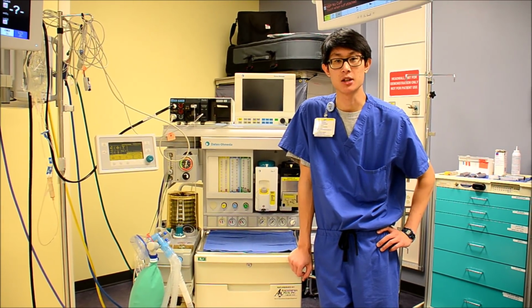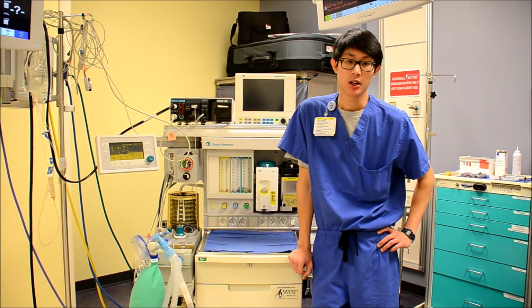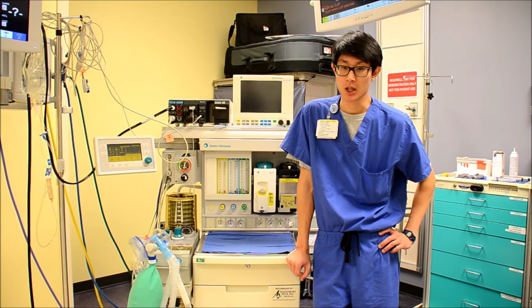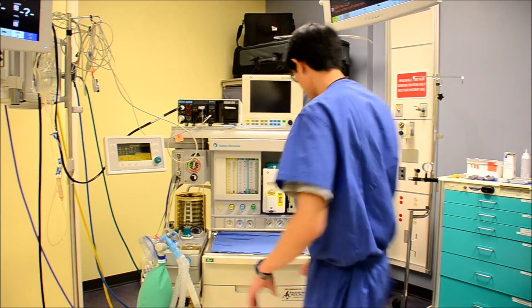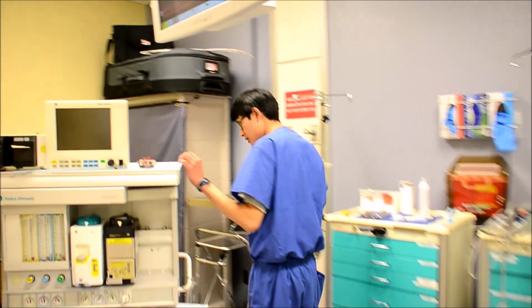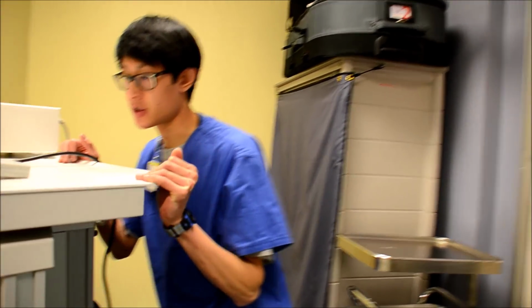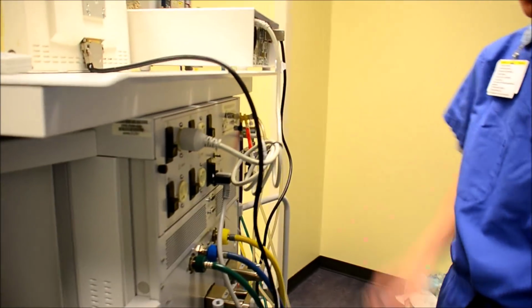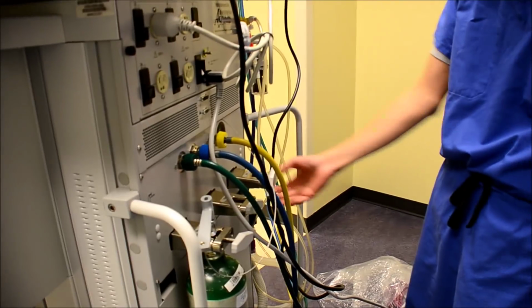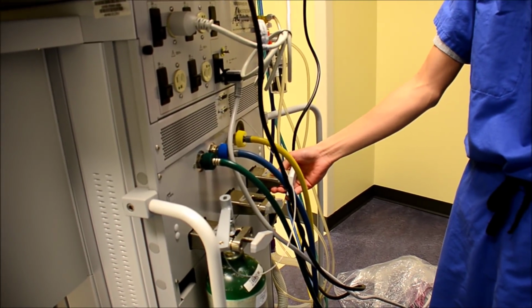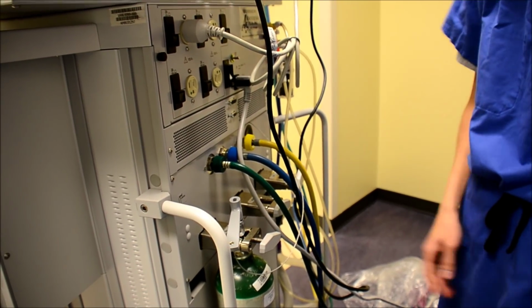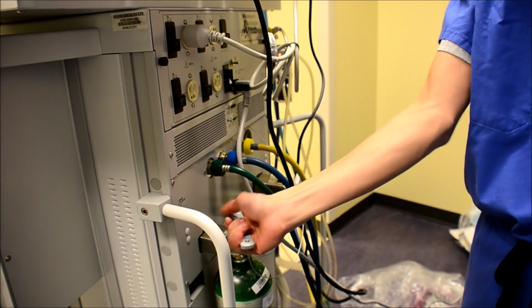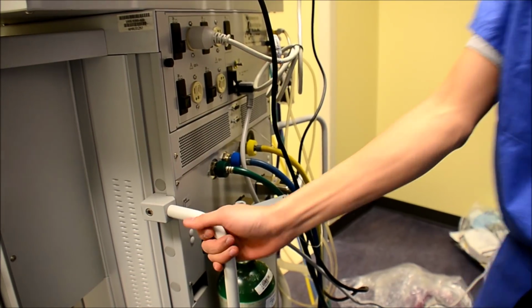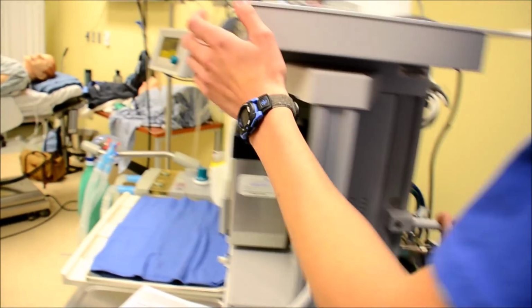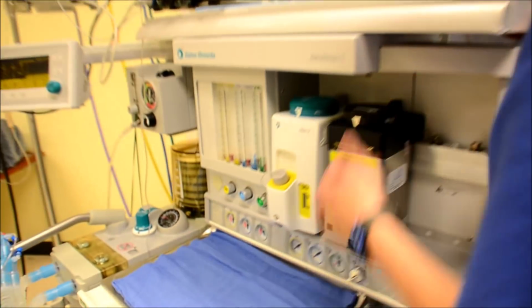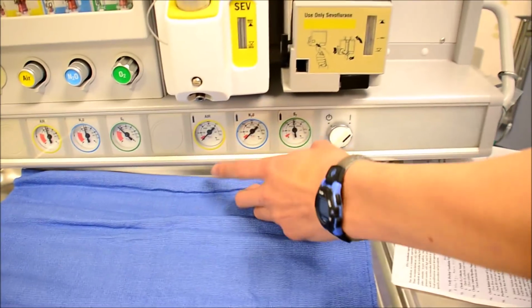So the next things we'll need to check are your pipeline and your cylinder supply. So in order to do that, we'll come to the back of the machine where you have your cylinders connected to your anesthesia gas machine. You have oxygen, nitrous, and air. It's always in the same format each time. So what you'll do is you'll crank each tank open in the morning, and you can leave it open. And we'll come around to the front of the machine and check our Bourdon pressure gauges.